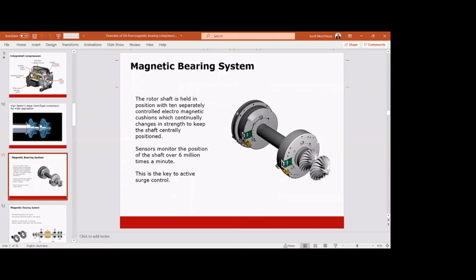And one of the key aspects of some technologies on the market is active surge control. So on conventional machines, when we look at a surge condition, we monitor the operating envelope, or the map, where we are on the map, and we also look at the amps. But on magnetic bearing technology, we look at the shaft and how unstable the shaft is becoming. So the more unstable the shaft becomes, the closer we are coming to the surge line. So we have what we call active surge control.